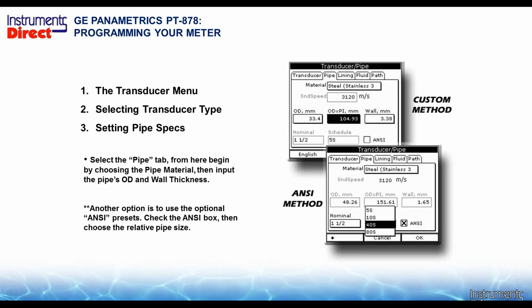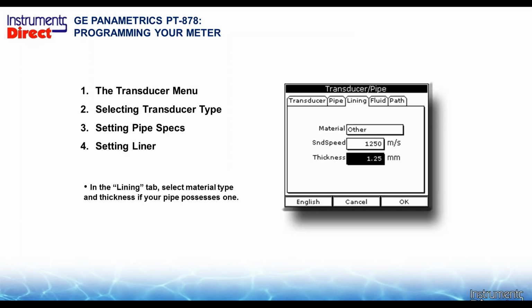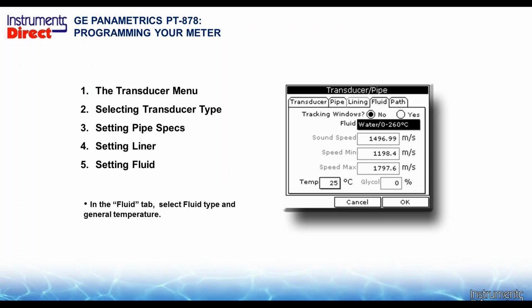So select your pipe size, select your schedule, and then after that, we're going to select if we had a liner. The only time you're going to see a liner is if you had unique Teflon or Kynar liner, but that's more of an exotic application, and it rarely happens there. If you're in the municipal market, you might see a cast iron or ductile iron application that has a mortar lining, and their linings are usually 1.25 or double that, but 9 out of 10 times it's 1.25 is the liner. So you put that information there. Again, as I showed you, as part of the calculation.